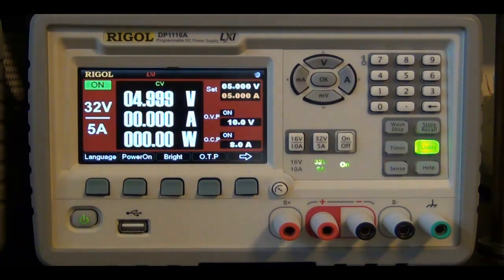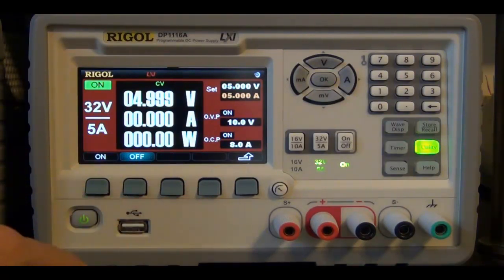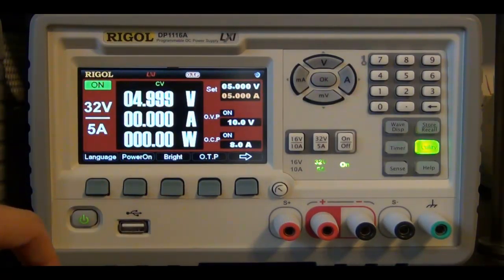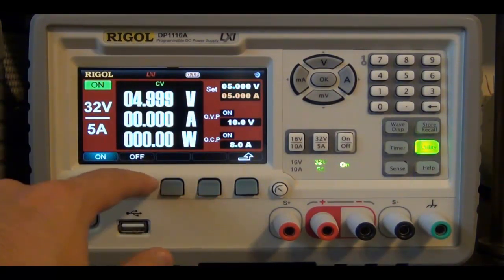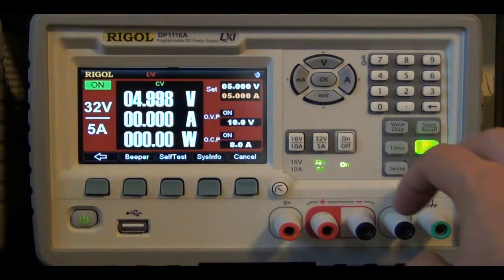It also has over temperature protection built into it. So on top of over current protection and over voltage protection, there's also OTP. And it has a two-stage OTP, meaning that I can enable the OTP button. So if the temperature exceeds a certain value inside the instrument, it will automatically turn the output off to prevent any damage to your circuit or to the power supply. It has a two-stage one, where the second stage of the OTP is internal, without your control. It will, of course, shut down if the temperature exceeds a certain value. So a very, very useful set of configuration.